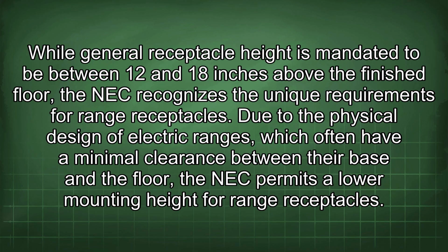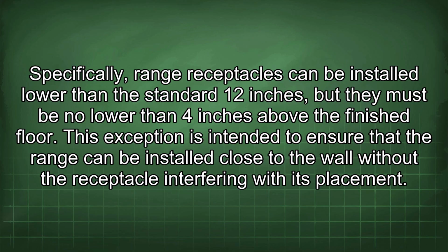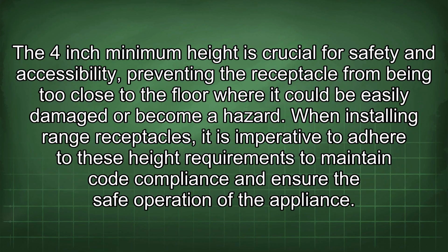Due to the physical design of electric ranges, which often have a minimal clearance between their base and the floor, the NEC permits a low mounting height for range receptacles. Specifically, range receptacles can be installed lower than the standard 12 inches, but they must be no lower than 4 inches above the finished floor. This exception is intended to ensure that the range can be installed close to the wall without the receptacle interfering with its placement. The 4-inch minimum height is crucial for safety and accessibility, preventing the receptacle from being too close to the floor where it could be easily damaged or become a hazard.